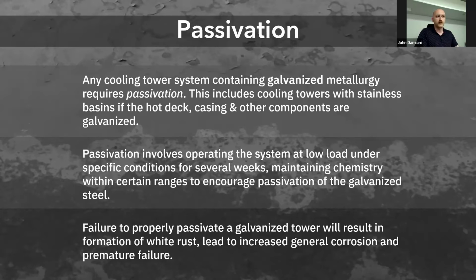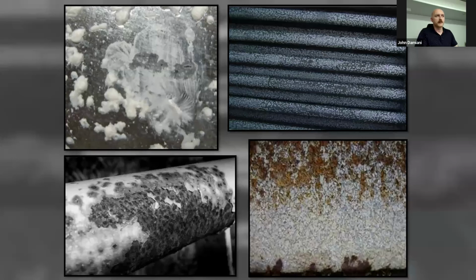Failure to properly passivate a galvanized tower will result in white rust formation. White rust is a compound of zinc, usually a complex zinc carbonate compound, and it appears as a waxy, powdery formation on the tower, on the heat exchange surfaces, and on the actual metal surface where the galvanizing is.